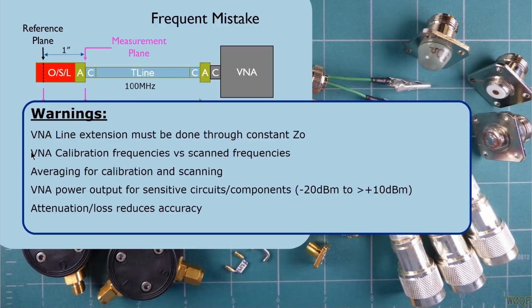VNA calibration frequencies and scan frequencies are a constant source of problems for people. You calibrate over a range of frequencies that you think is adequate, but then you scan later at some incredibly small range of frequencies, and the VNA is responsible for doing some interpolation between the frequencies. If the VNA was calibrated at, say, 9 megahertz and 10 megahertz were the 2 points, and you're using it at 9.5, the VNA needs to interpolate the 9 megahertz value and the 10 megahertz value to get 9.5. How it does that is a function of the VNA software. You could do it with some kind of curve fit, which would be good. It typically probably does it as a straight line fit. I know how my analyzers work, but it's something to keep in mind.